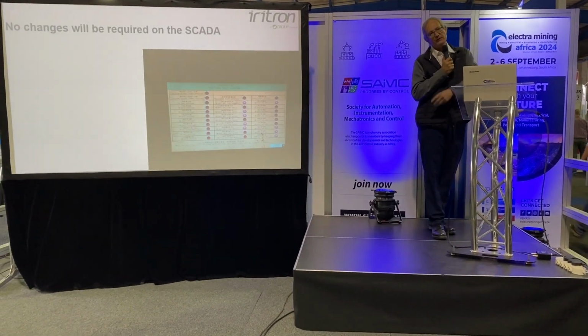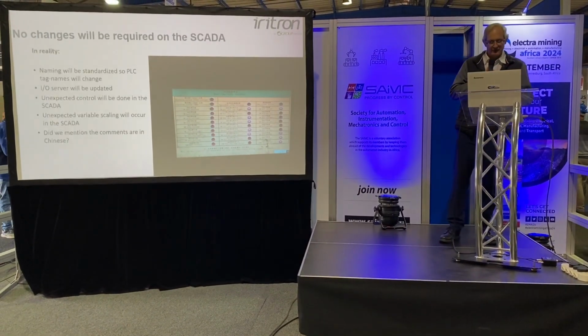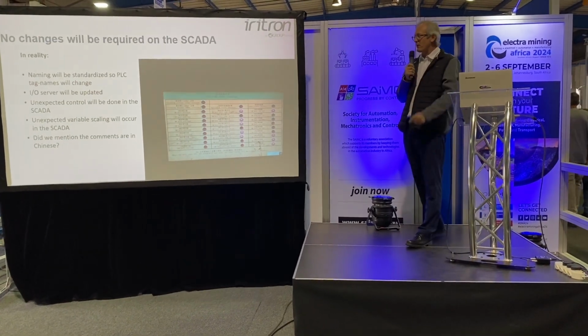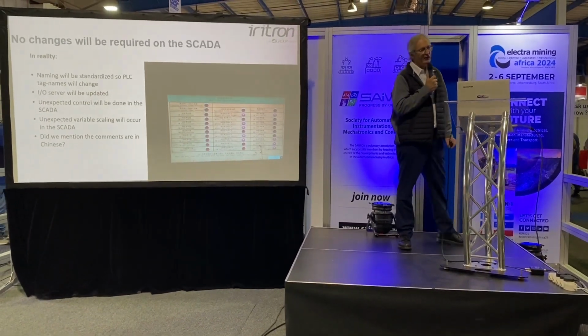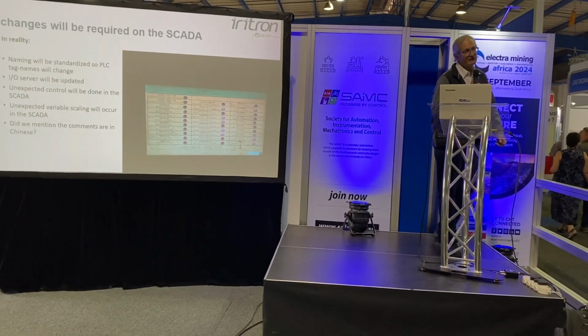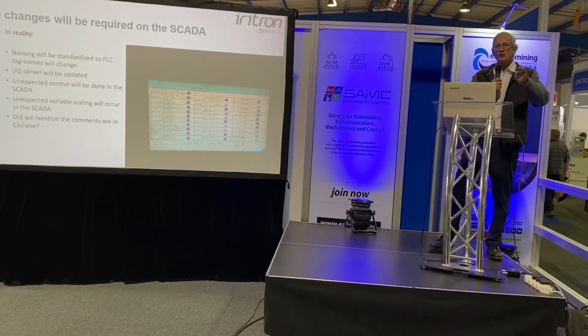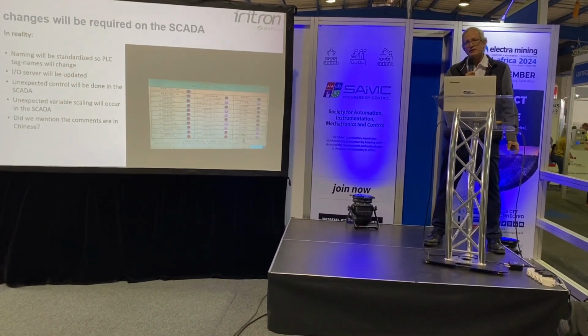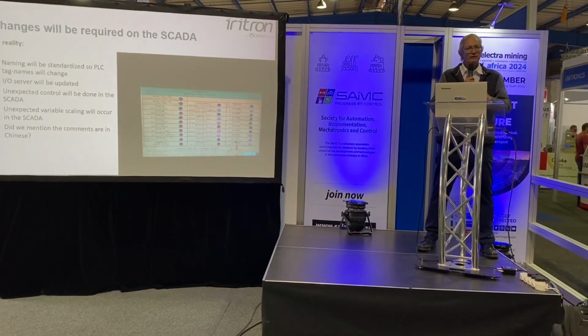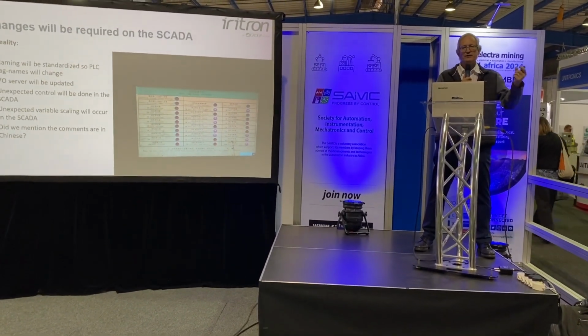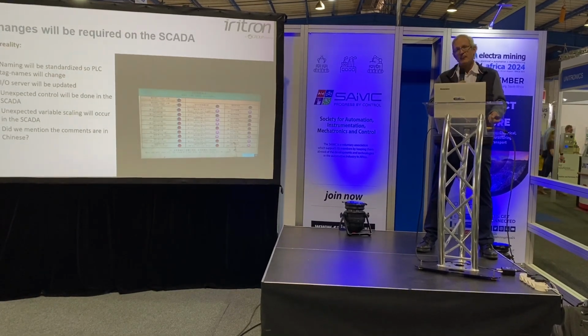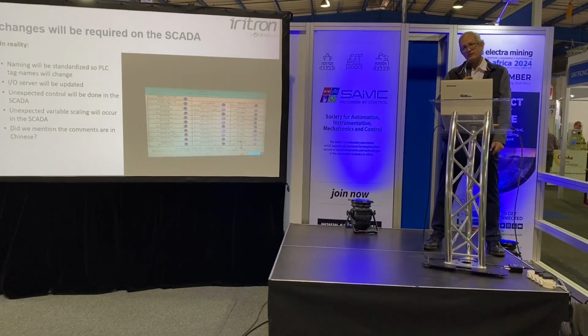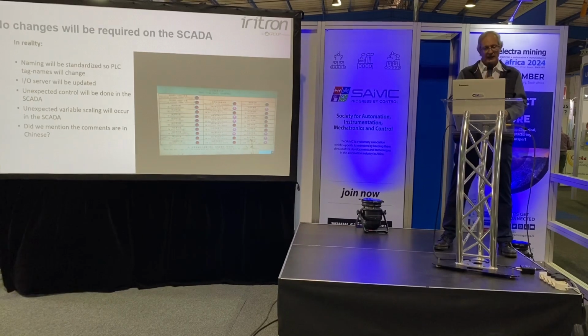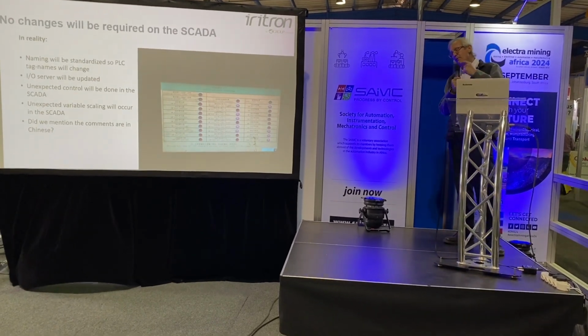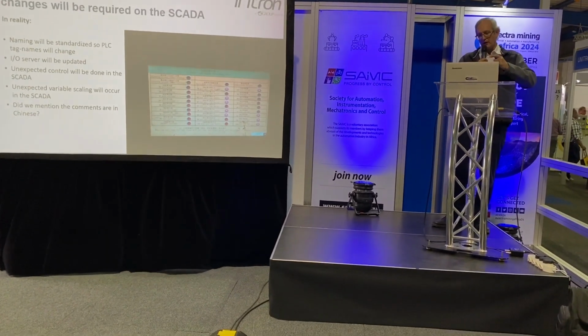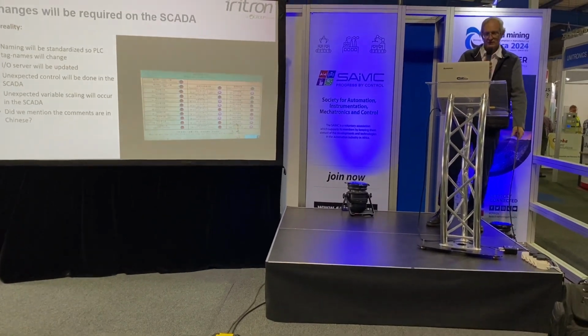So remove the Chinese, which is the smallest of the problems, because what we actually find is that on the SCADA side, because you're changing the naming convention in the PLC, your SCADA will change. You'll need to change the naming in the SCADA. You'll need to change the naming in your IO server, because the naming convention has changed. Your PLC addressing has changed. Your communication protocols and your communication hardware has changed.